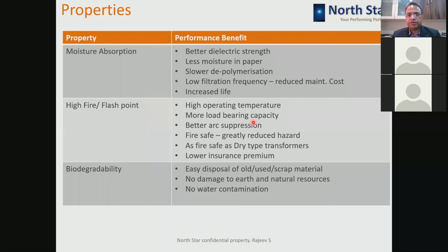So more load bearing capacity is another benefit of using natural and synthetic ester. Because they have a high flash point, they have excellent arc suppression capabilities compared to mineral oil. So if any arcing happens, which is common in OLTCs, the chances of catching fire because of arcing are less. And since the arc is getting suppressed, deterioration of the contacts in the OLTC is also very less. So the maintenance frequency of the OLTC will also get extended because of this better arc suppressing property.